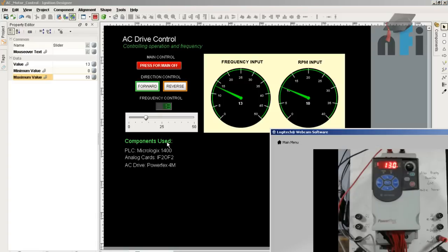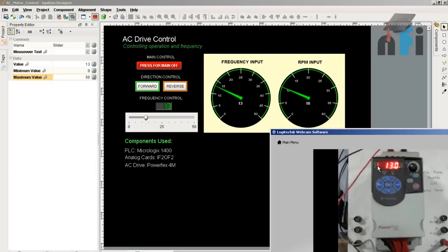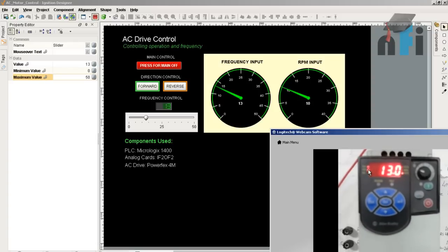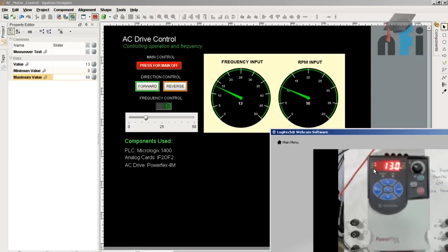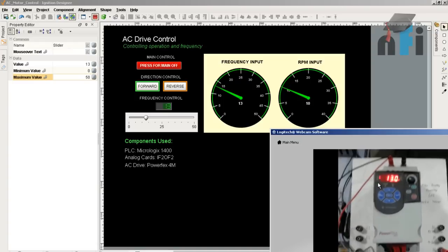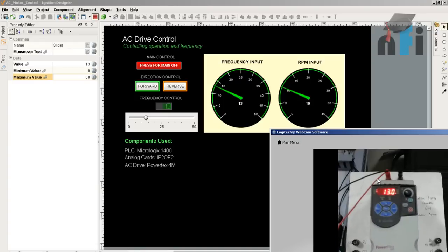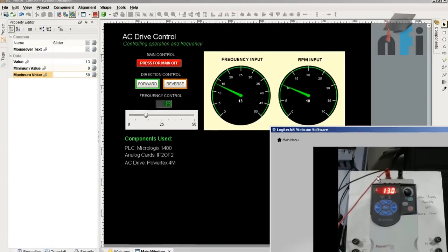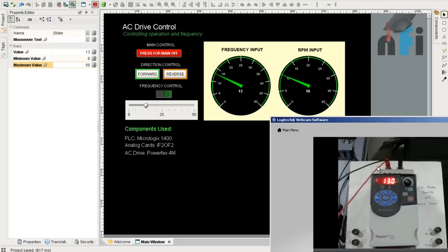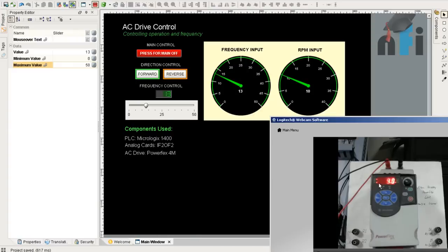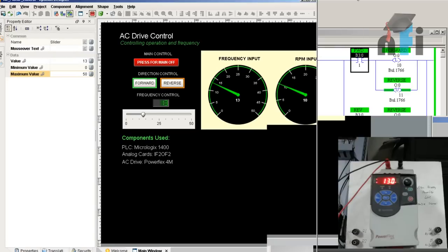Forward is running because if you see closely, it has three LEDs: the first is for run, second is for forward, third is for reverse. So this is running in forward direction. This drive is connected to a conveyor. When I press on reverse, this will make the drive run in reverse direction. You can see the below LED - this is the indication of reverse at 13 hertz.